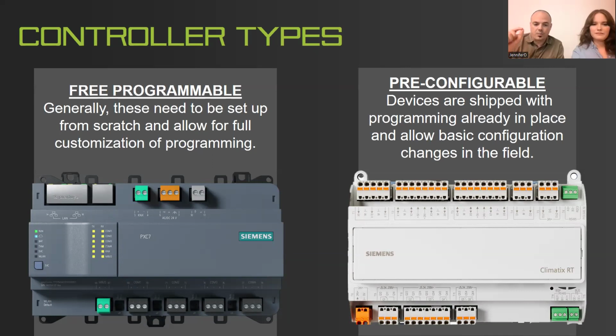On the pre-configurable side, the device shows up from the factory with the program already intact. Instead, it presents the field technician setting it up with a series of options that usually look like a checklist — is there an economizer on this unit? Yes or no. Is there a return air fan? Yes or no. A discharge air temperature? Yes or no. The technician looks at their current application and checks all the boxes that apply, and the internal programming runs to maintain as expected.